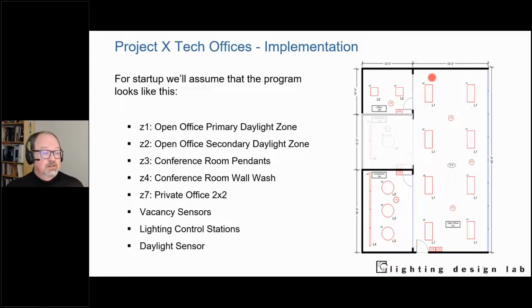If this was Luminaire Level lighting control approach, we would have a sensor in each one that would be a closed loop sensor looking down, and it would be essentially modifying the light output on a per fixture basis, right? So it's automatically becoming its own primary and secondary daylight zone. Now, all that said, you can do some advanced programming if you want to, and for some systems, have the signal from each one of these sensors aggregated and averaged, right? From a Luminaire Level lighting control standpoint in both cases.